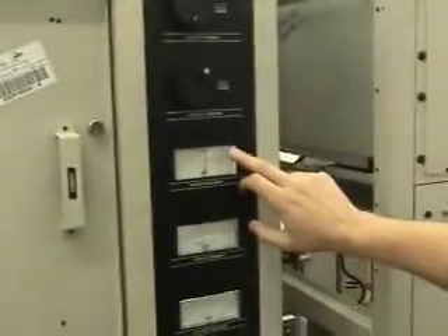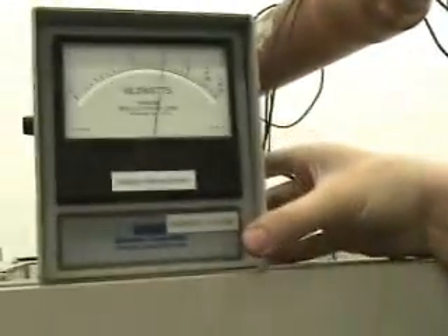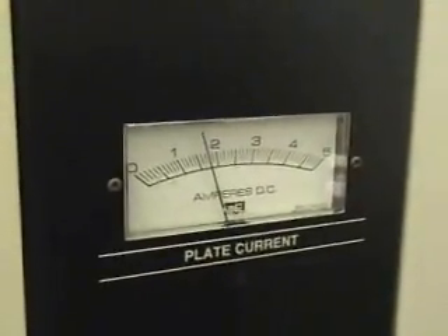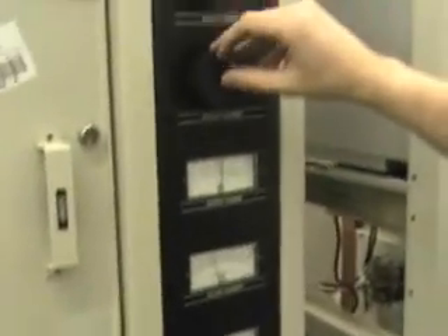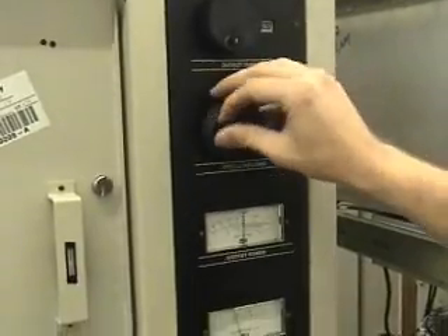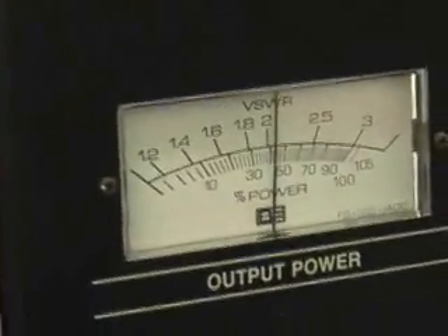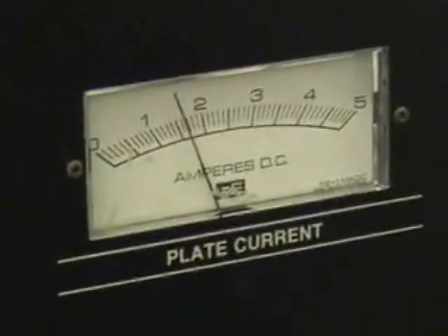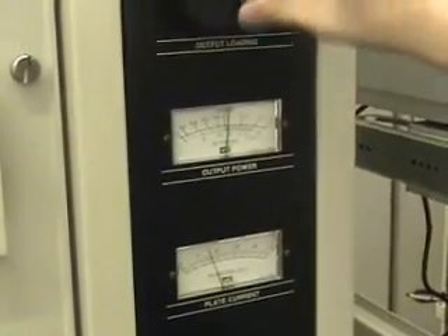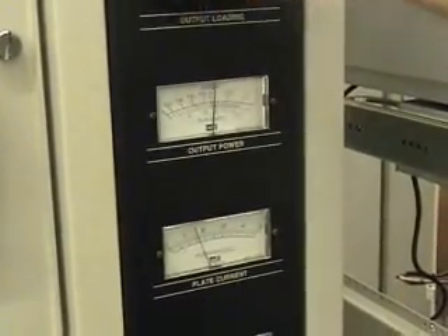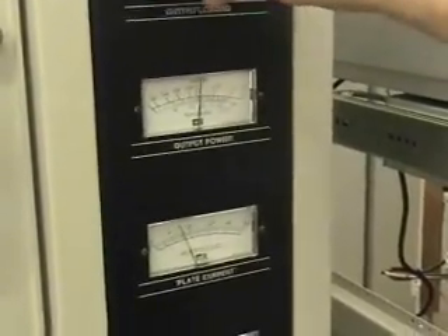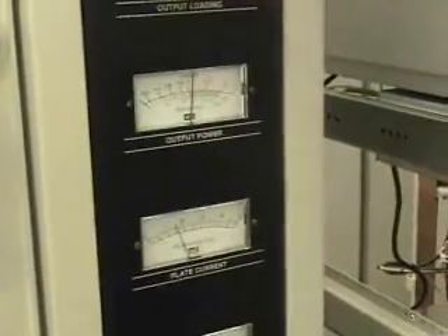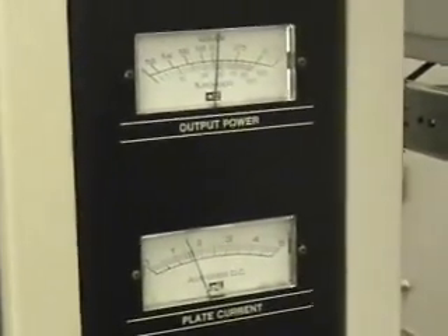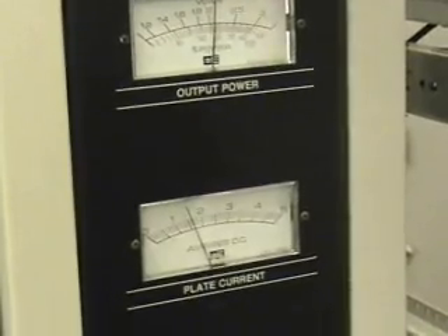And then right away I'm just looking at the forward power, and if you have an external watt meter inline section, you can look at that, and you're looking at the current. So I just start with loading, and I peak that, and you're going to dip the current, for as little current as possible, but as much RF as possible. When you see the forward power meter start to fall, then you know you're peaked out there. You go next to your output tuning. Tune back and forth for as much forward power and as little current. You can see we're peaked there.